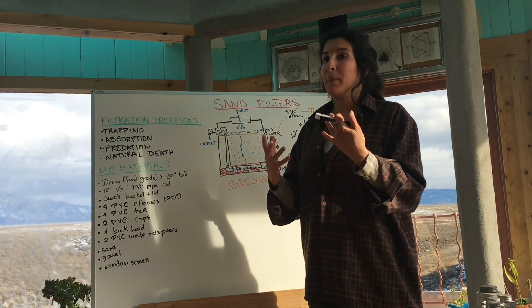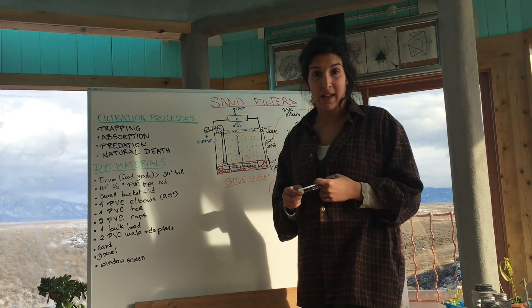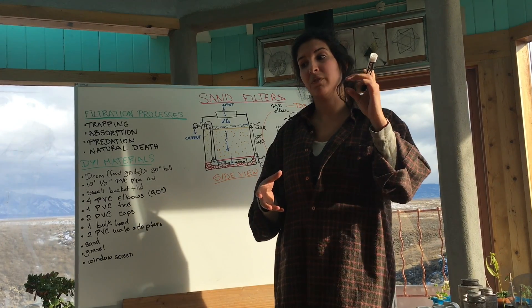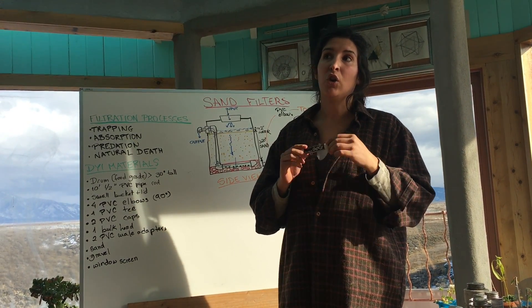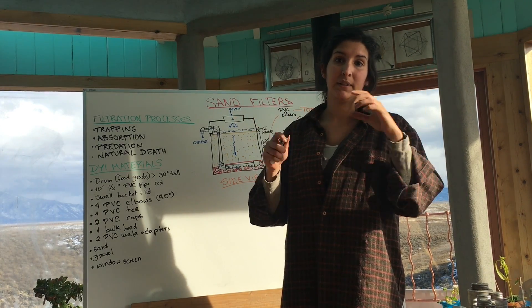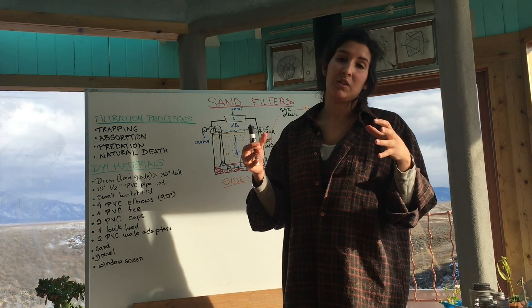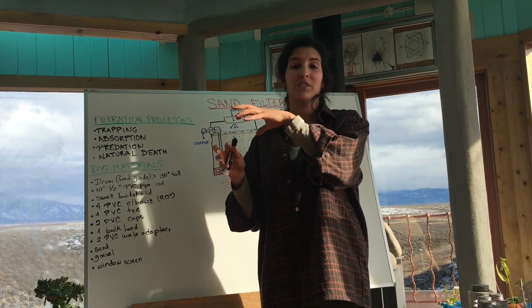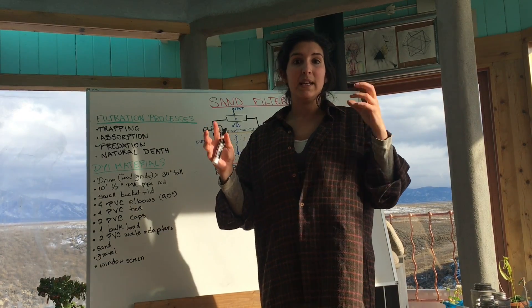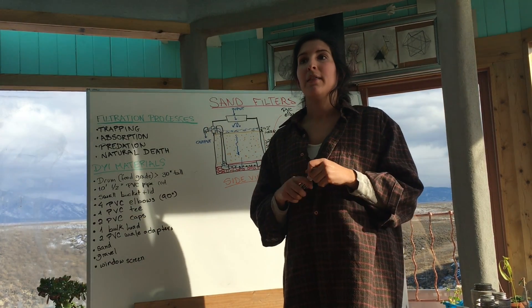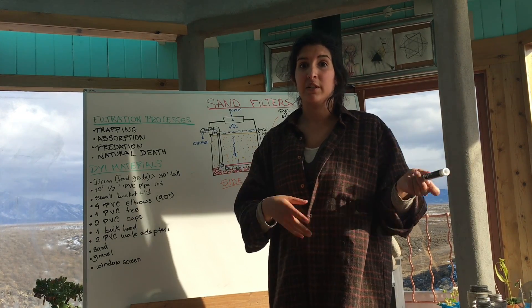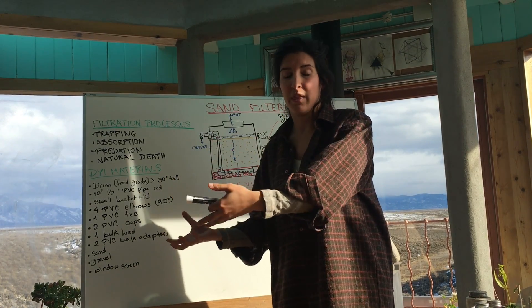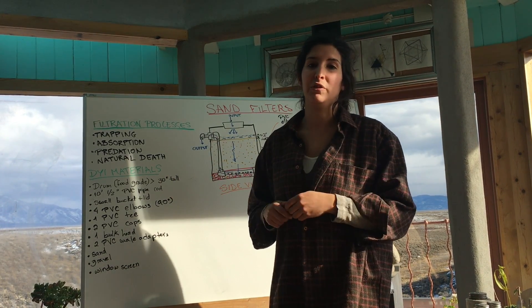The way they work: their main component is sand, and most of the filtration — some of it happens in the sand, but most of it happens right on top of the sand. This is called the bio layer. On the bio layer there is a little ecosystem that establishes basically microorganisms that live on the surface of the sand, that eat and predate on the viruses, bacteria, and other microorganisms that come with the water that you want to filter.